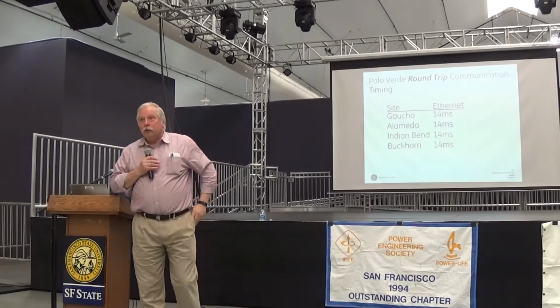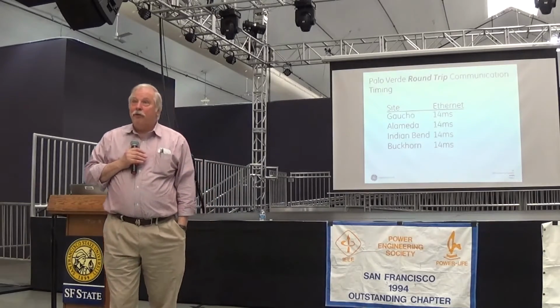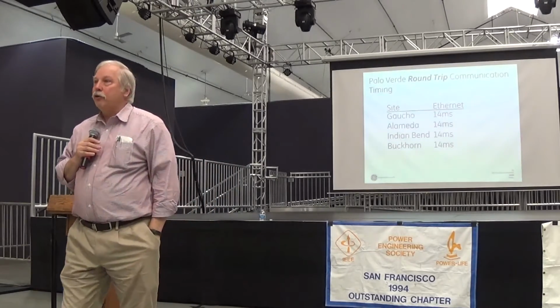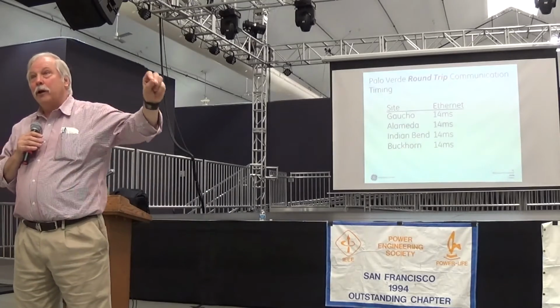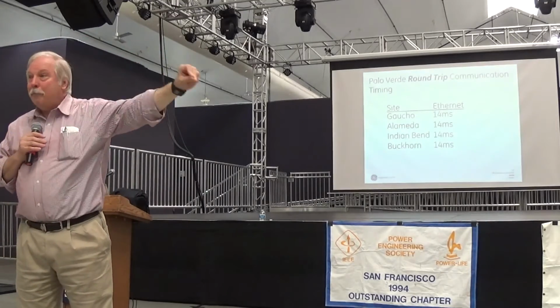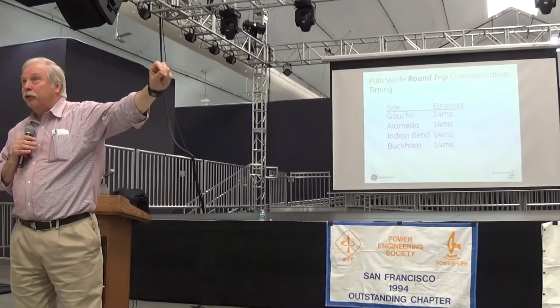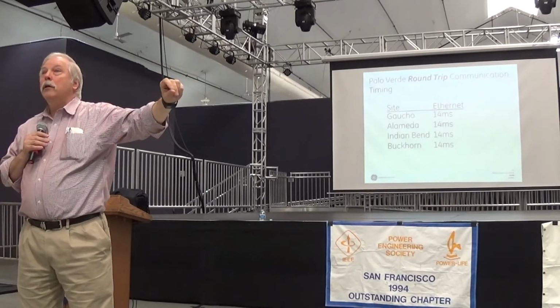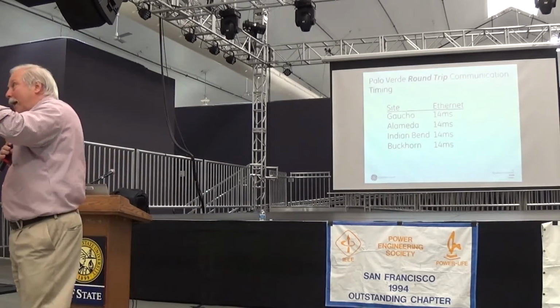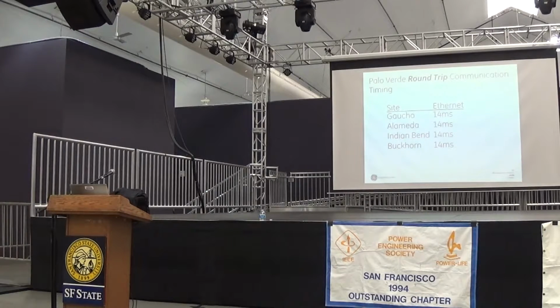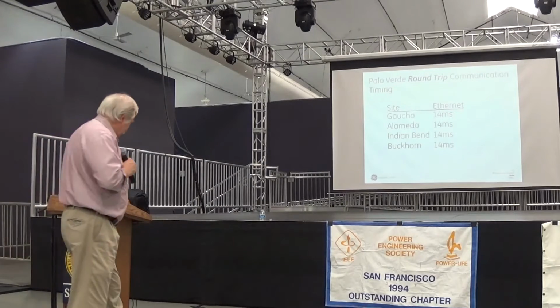In doing testing of the system, the round trip time from Palo Verde to a substation and back again, round trip measured time, is 14 milliseconds. That means one way messaging time to hit all those substations is 7 milliseconds using Goose messaging.